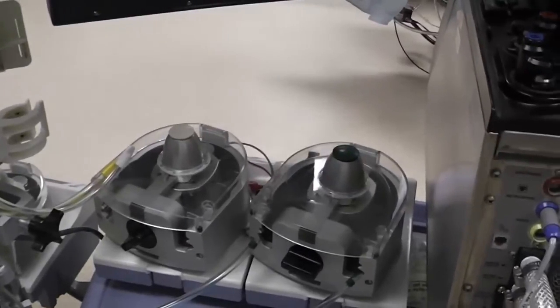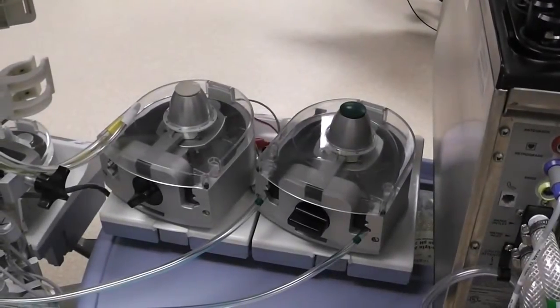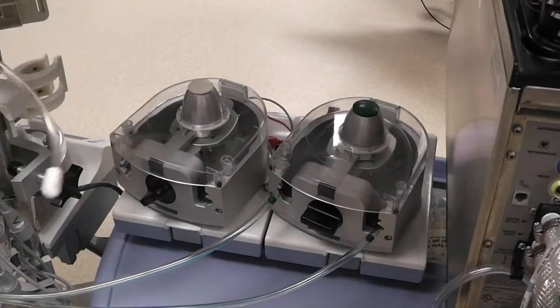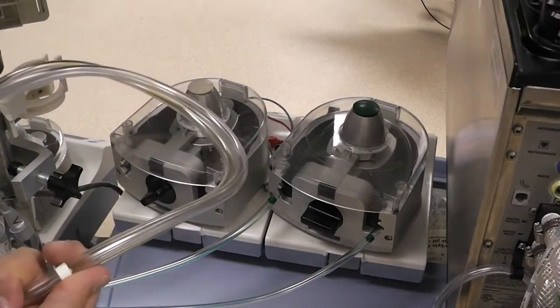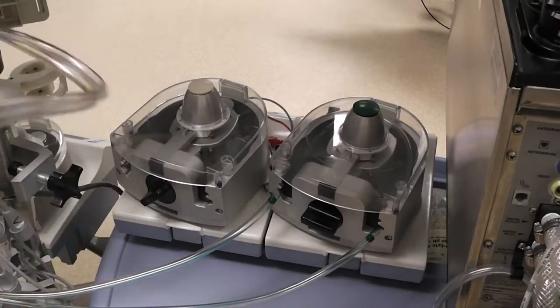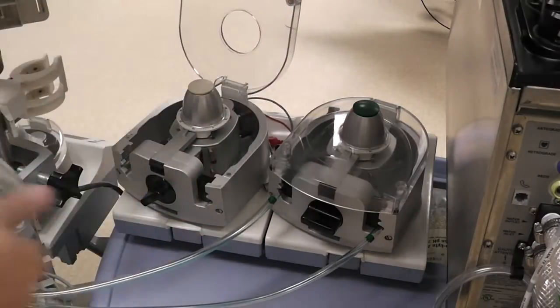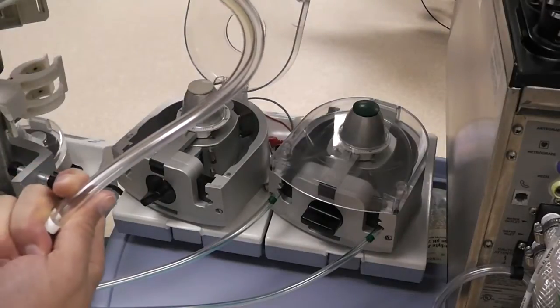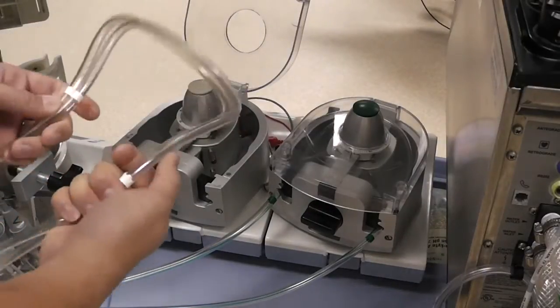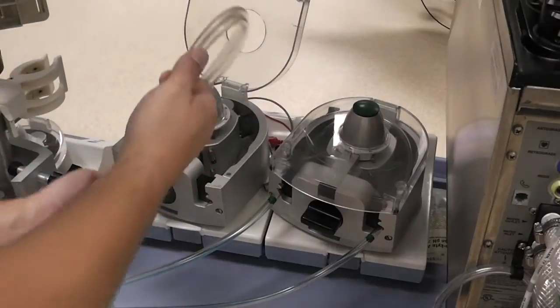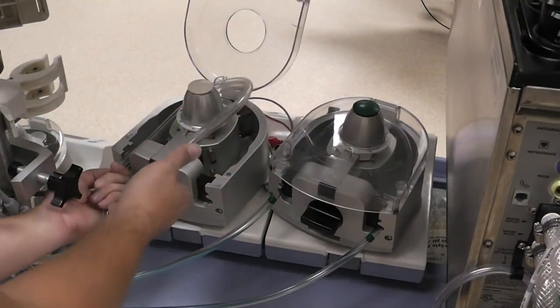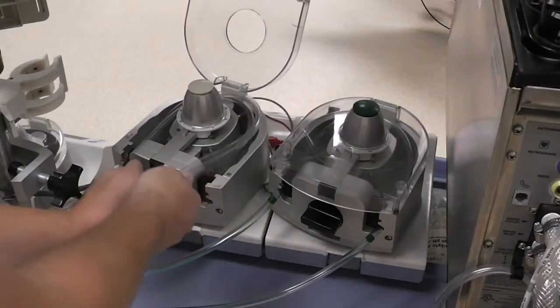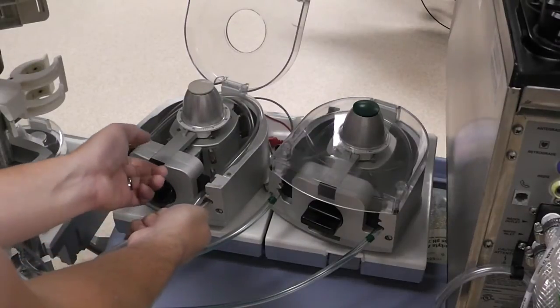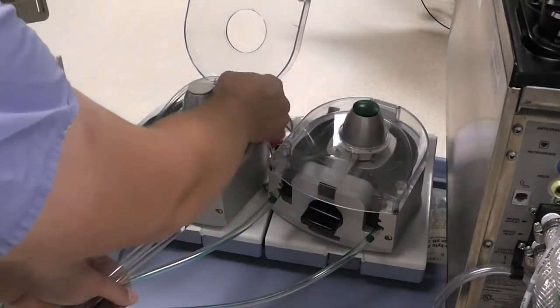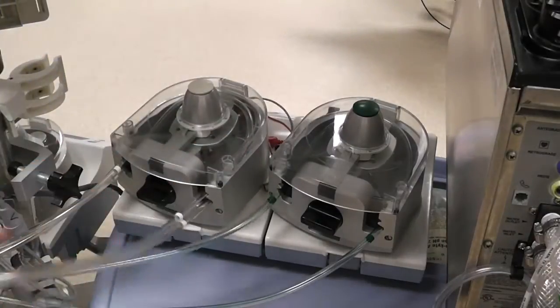I apologize for this camera here, but this is all I've got to work with. So the sucker lines are a little different just in that there are two lines. There's a white line and a yellow line, but they go in the same way. You just set them one on top of the other, trying to keep the tapes lined up. Open up the side just as with the vent, put them into the pump head, and then close the lid.